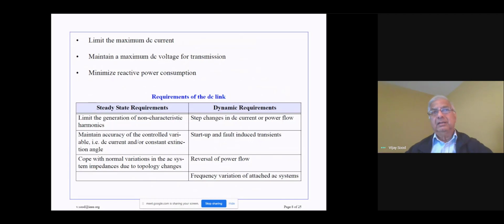The second objective is to maintain the DC voltage to make sure that we do not exceed a certain maximum value. Again, insulation requirements determine what is the maximum DC voltage for transmission purposes. We want to have a maximum voltage because we want to maximize the power flow. So in order to keep the flow of power as high as possible, we want to maintain a high voltage. But there is an upper limit to how far we can go in reaching that maximum. And finally, the controls have the objective to minimize the reactive power consumption at the AC side of the system. Minimizing the reactive power consumption means that the delay angles, the commutation angles, and the extinction angles must be kept as low as possible.